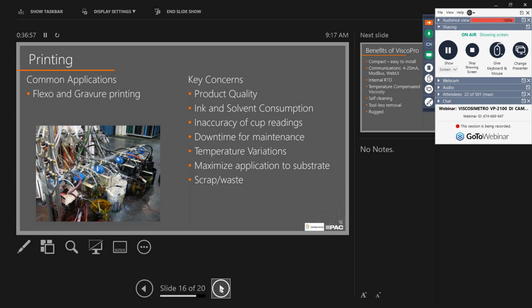So all of these have overlapping concerns, and the number one being quality. And also, you know, if you're investing in a device like this, to be able to get a return on investment based on material scrap. So, you know, a lot of quality issues are driven by inaccurate indicators like cup seconds, where there can be a variation of 4 seconds or more from operator to operator. And they're also driven by temperature fluctuations.